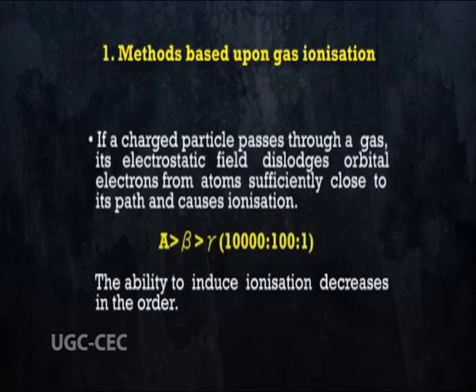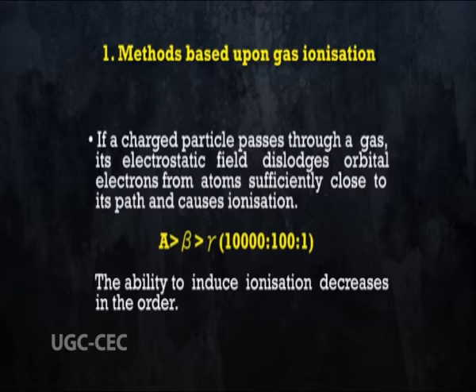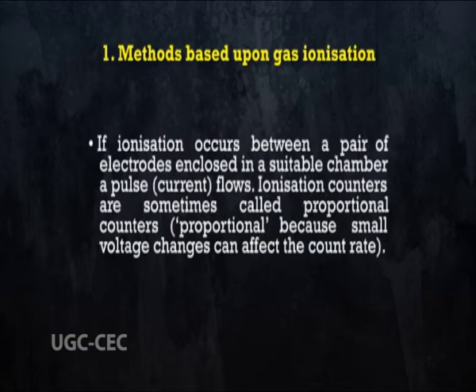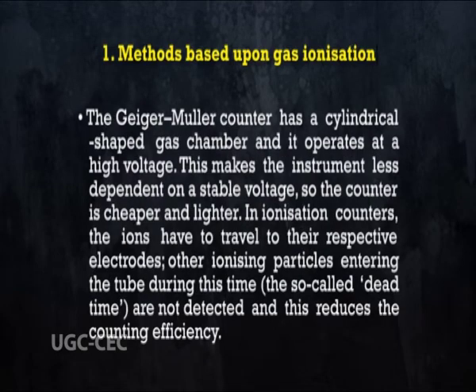The first method is based upon gas ionization. If a charged particle passes through a gas, its electrostatic field dislodges orbital electrons from atoms sufficiently close to its path and causes ionization. The ability to induce ionization decreases in order. If ionization occurs between a pair of electrodes enclosed in a suitable chamber, a pulse current flows. Ionization counters are sometimes called proportional counters — proportional because small voltage changes can affect the count rate. The Geiger-Muller counter has a cylindrical shaped gas chamber and operates at a high voltage, making the instrument less dependent on a stable voltage, so the counter is cheaper and lighter.